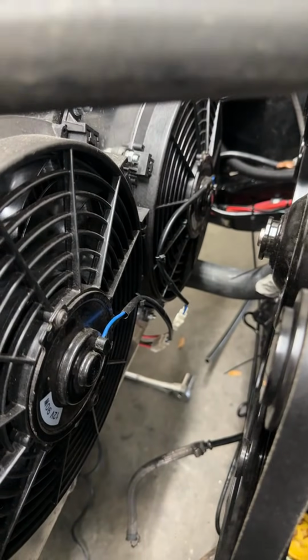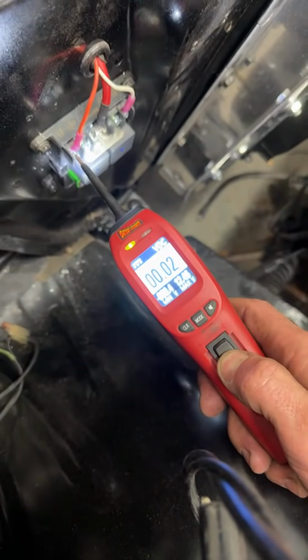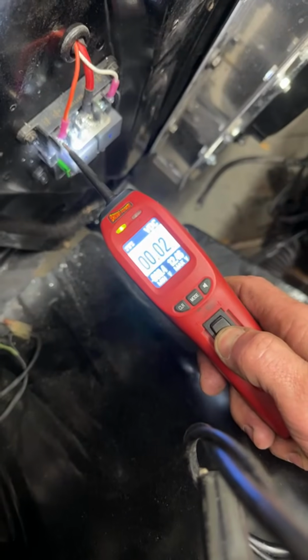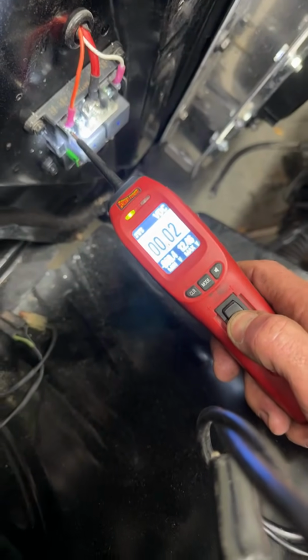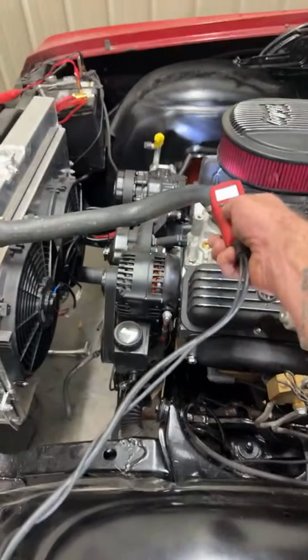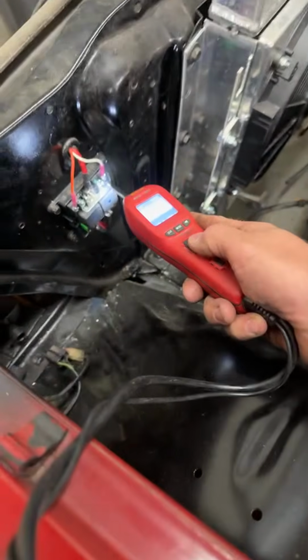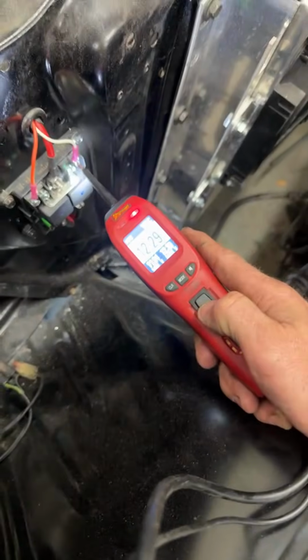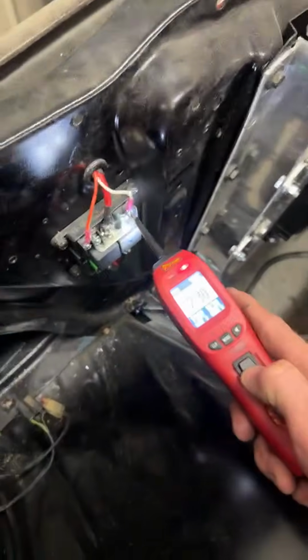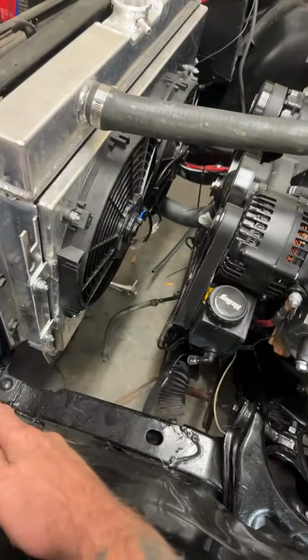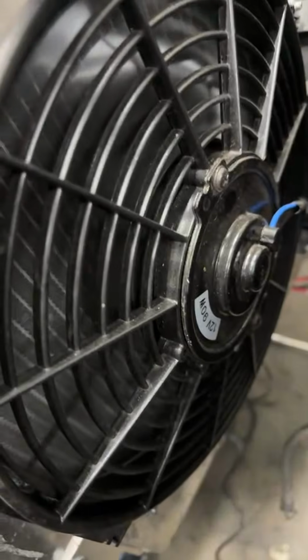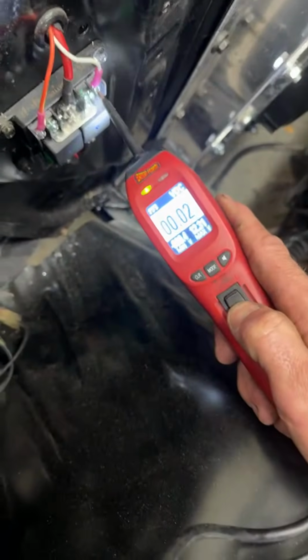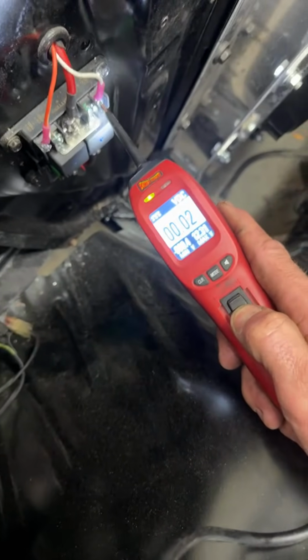The fan comes on. Now we got a fan. And look, it's only pulling 0.02 volts on the negative side, right? Now, once that sensor hits 190, because we got it set up on the handheld, we want fan number 2 to come on at 190. This is fan number 2, right? So when it tells it, hey, look, I need fan 2 to come on, that thing's hit 190 degrees, it sends a signal on the ground side. It activates the fan. Fan 2 comes on. See that? Fan 2 on. Look, we're only pulling 0.2 volts, or 0.02.